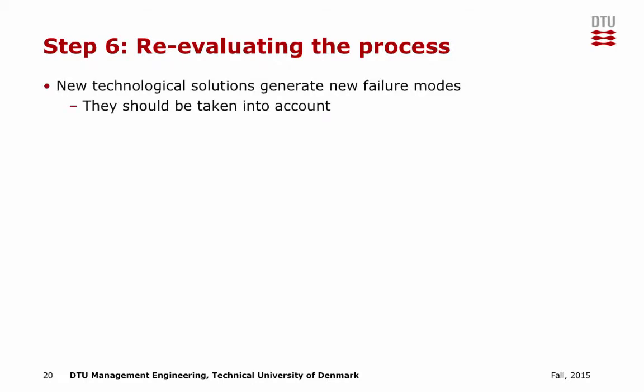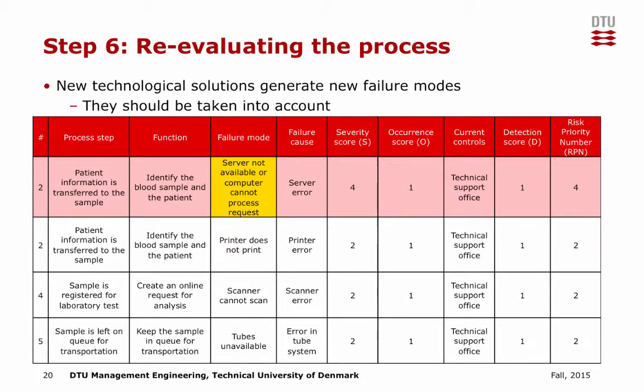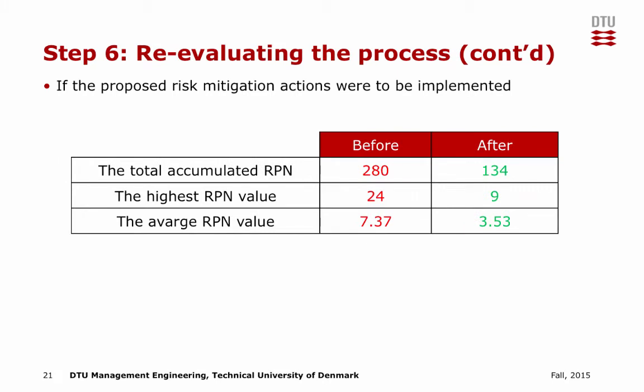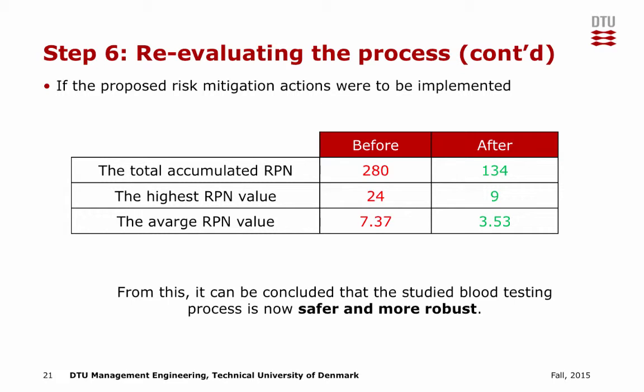In step 6, the process is re-evaluated. It should be noted that new technology solutions generate new failure modes that should also be taken into account. For example, for the failure mode of incorrect data, the risk mitigation was to introduce a computer system and automatic printers. With that, a new failure mode has been created: a server failure may now influence the outcomes of the process, and this new failure mode needs to be evaluated as well. If the proposed risk mitigation actions were implemented, the total accumulated RPN would decrease significantly from 280 to 134. The new highest RPN score of an individual failure mode would go from 24 to 9, and the average RPN value would decrease from 7.37 to 3.53, concluding that the blood testing process is now safer and more robust.